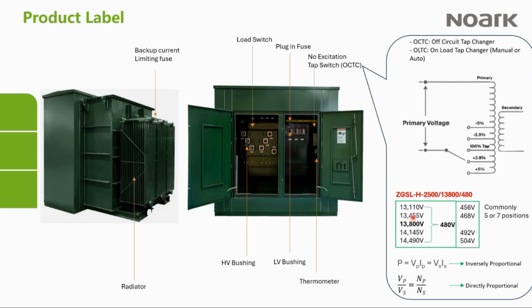Basically, a tap changer is a series of windings in a transformer that allows you to select. So this is how it works. You can have a 5-position tap changer, and in this case, this is a 5-position. The first position is the 100%, right? It has that 13.8 kV. Then it has plus 2.5%, and that gives you 13,455 volts. Sorry, I'm saying it the other way around: minus 2.5%, and then minus 5%. So the tap changes every 2.5%, plus or minus 2.5% on this side and on this side.